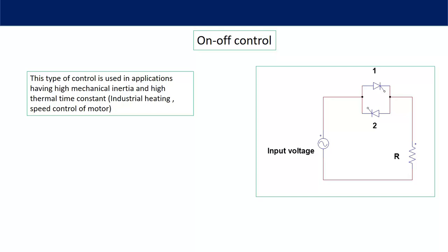Similarly, in industrial heating — suppose you want to heat a furnace up to 1000 degrees centigrade. By applying input voltage, the furnace is heated to 1000°C. Once it reaches that temperature, the supply is removed. As the thermal time constant is very large, the temperature will not instantly drop to a lower value. It is allowed to decrease up to an allowable limit, and then the input voltage is reapplied to heat the furnace again. This cycle continues and saves a lot of energy.